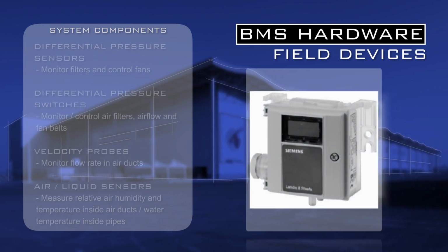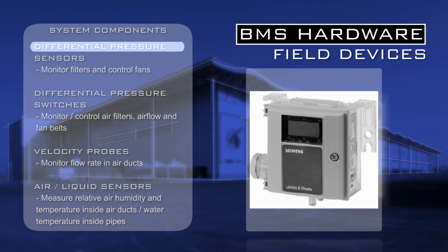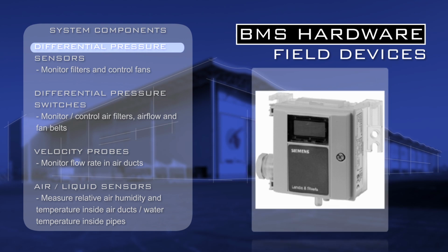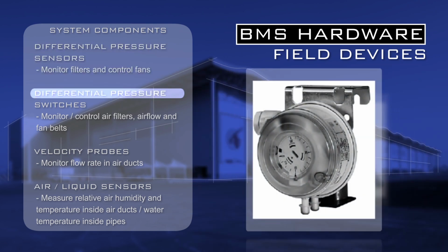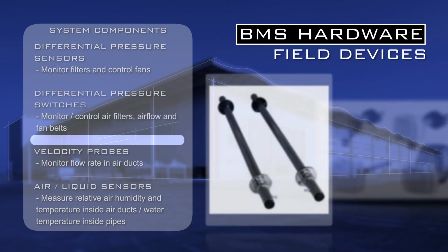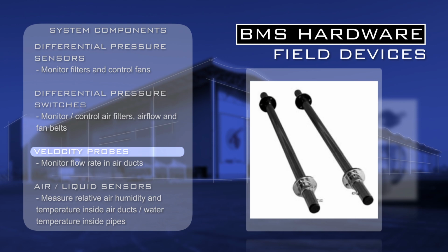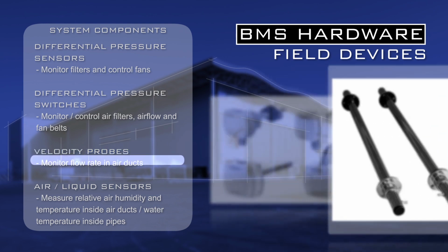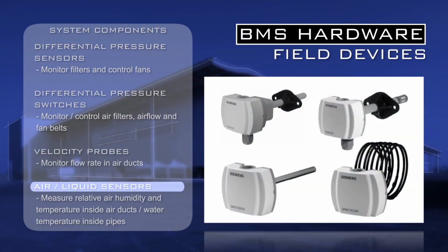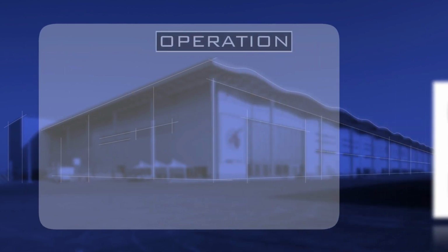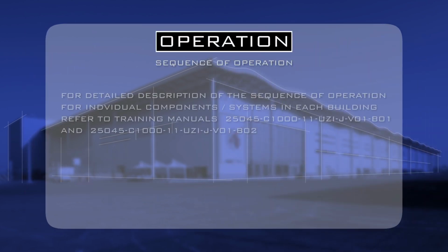Field devices also include differential pressure sensors, which monitor filters and control fans. Differential pressure switches, which monitor and control air filters, airflow, and fan belts. Velocity probes, which monitor the airflow rate in the air ducts. And air and liquid sensors, which measure the relative air humidity and temperature inside the air ducts and water temperature inside the pipes. For a detailed description of how to operate the individual components and systems in each building, refer to the relevant manual.